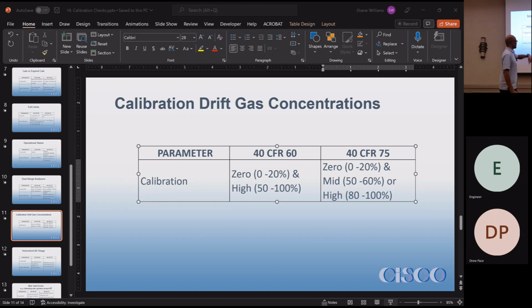clean of O2. Oh, it's clean of O2 interference. And basically, the only interferent that has a significant effect is if you have a 500 ppm NOx as part of your instrument error. That's the only thing in the table we've reviewed that shows it can cause it. So basically most instrument error, but how do you demonstrate that fact? One of the methods we kind of use to demonstrate is when you're doing other tests using O2 as a zero gas and it has no impact on your NOx value, you're not seeing any NOx reading. It shows there's not enough NOx in there. There's not 500 ppm of NOx in your instrument air.